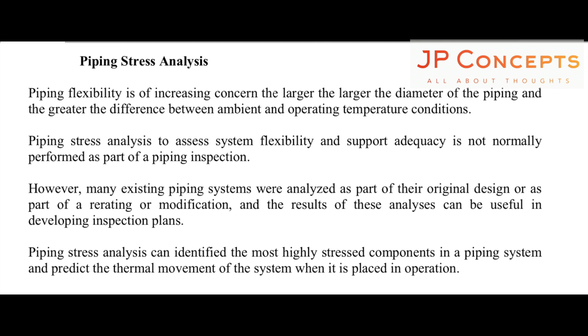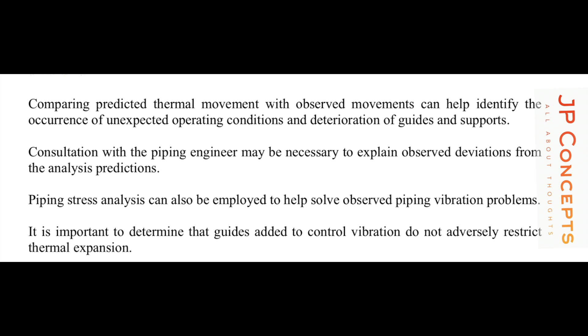Comparing the predicted thermal movement with the observed movement can help to identify the occurrence of unexpected operating conditions and deterioration of the supports. Consultation with the piping engineer may be necessary to explain observed deviation from the analysis predictions. Piping stress analysis can also be employed to help solve observed piping vibration problems. It is important to determine that guides added to control vibration do not adversely restrict thermal expansion. When we are choosing the vibration dampers or vibration control devices, a lot of calculations should be done.